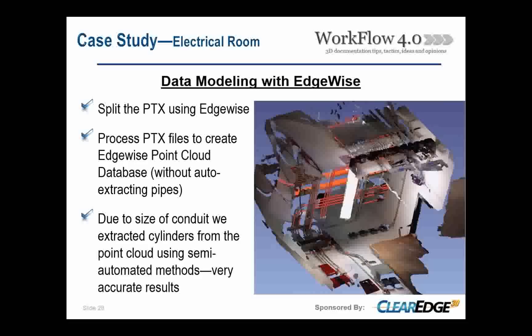We brought the PTX scan into Edgewise. The exports from handheld scanners are substantially smaller than from big tripod scanners, so processing doesn't take nearly as long. However, due to what we were trying to capture — lots of small-bore conduit, one-inch and three-quarter-inch conduit — we didn't spend enough time gathering enough points on those small bore conduits, so Edgewise was having a hard time finding them. Rather than using automatic extraction, we ended up using the manual extraction to identify and pull the conduit, then connected everything using Edgewise's user-friendly cleanup and standards-application methods.